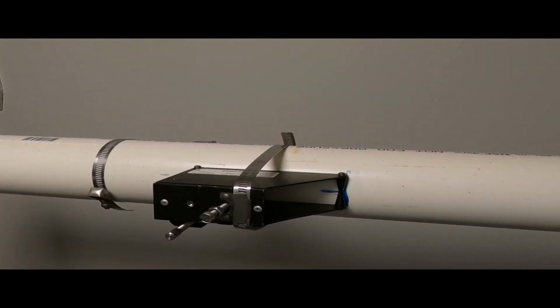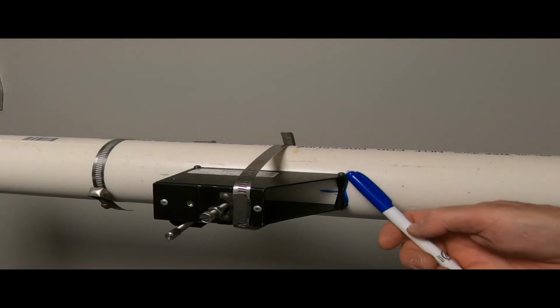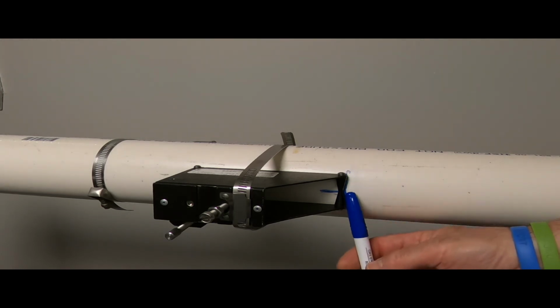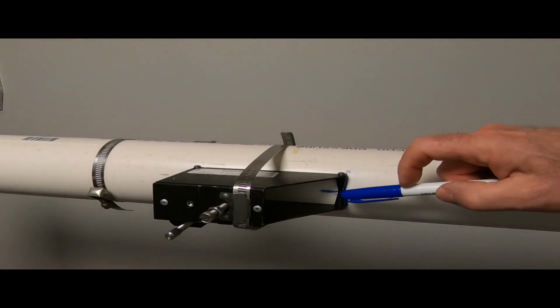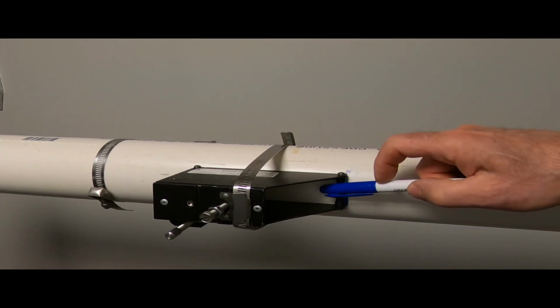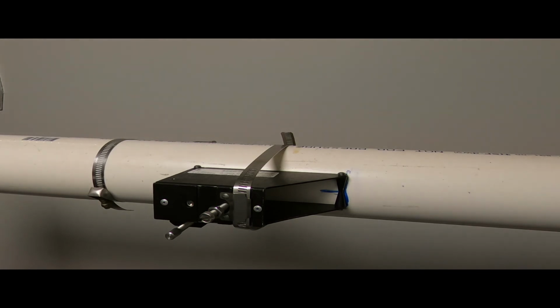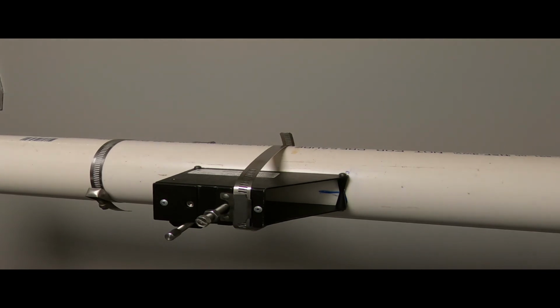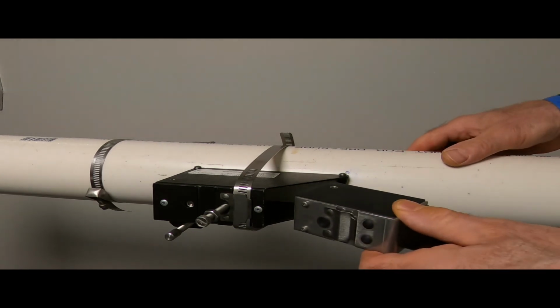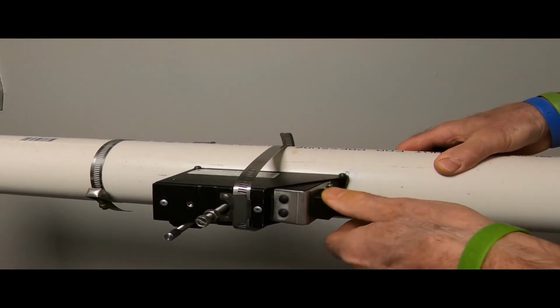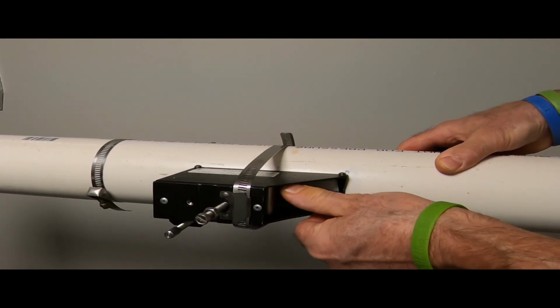As you can see now, our mounting frame is strapped in place. The back edge of the mounting frame is aligned with the circular mark we made on the pipe, and it is dead centered on the line we made along the pipe's axis. Again, this ensures that the two frames are exactly 180 degrees apart and at the correct spacing that was established by the spacer bar. We're now ready to install our flow sensors into our mounting frames. Be sure to use the correct coupling compound before doing so.